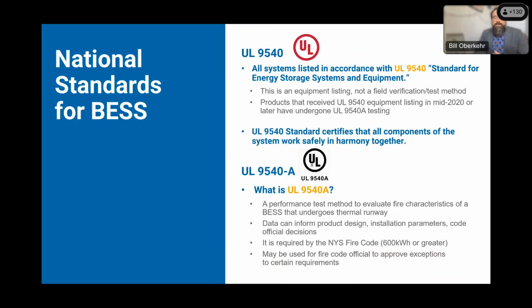I want to get into some of the national standards for energy storage systems, and I think these are the two most important from the product, meaning the equipment, point of view. New York's code, as well as national standards like NFPA 855 and the International Fire Code, all incorporate these standards by reference. So the New York code requires both a UL 9540 equipment listing and UL 9540A test data.